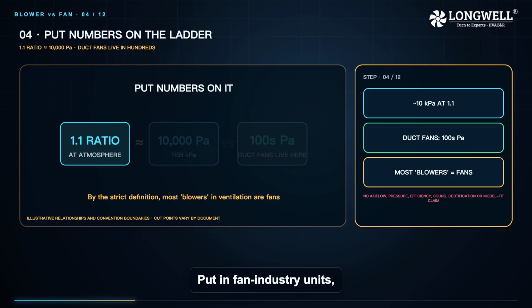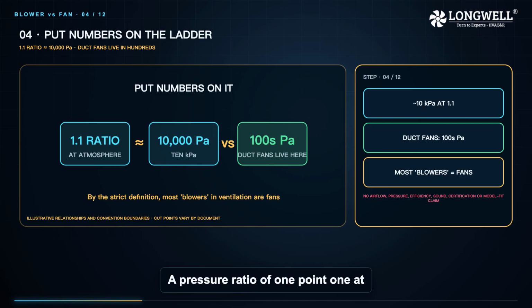Put in fan industry units, the numbers become vivid. A pressure ratio of 1.1 at atmospheric inlet is roughly 10 kilopascals, 10,000 pascals. The duct fans this series usually discusses work in hundreds of pascals. So by the strict definition, almost everything in ordinary ventilation, including machines everyone calls blowers, sits firmly in the fan category. The squirrel cage blower in a furnace is, formally, a fan.